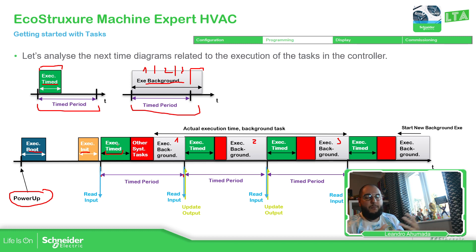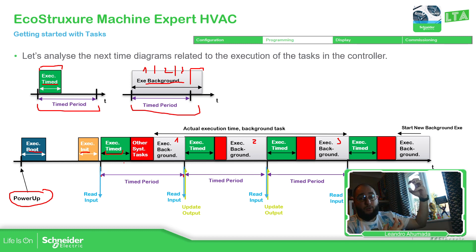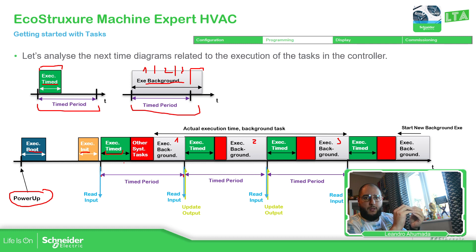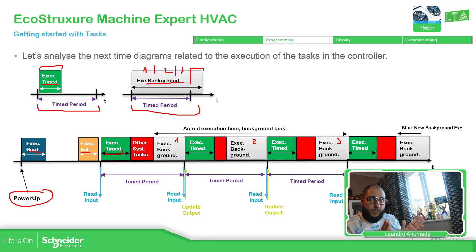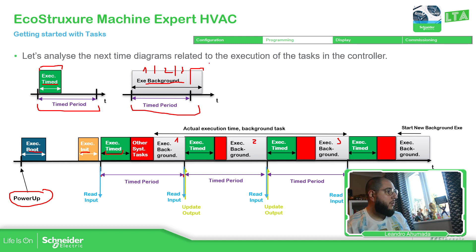Here you can see the priorities clearly. At power-up: boot task first, then init, then we enter the PLC scan cycle — read inputs, execute code, update outputs. During code execution we have the timed task, some system tasks, and then the background execution, which can be partial or total depending on the configured time period. That is how this part works.